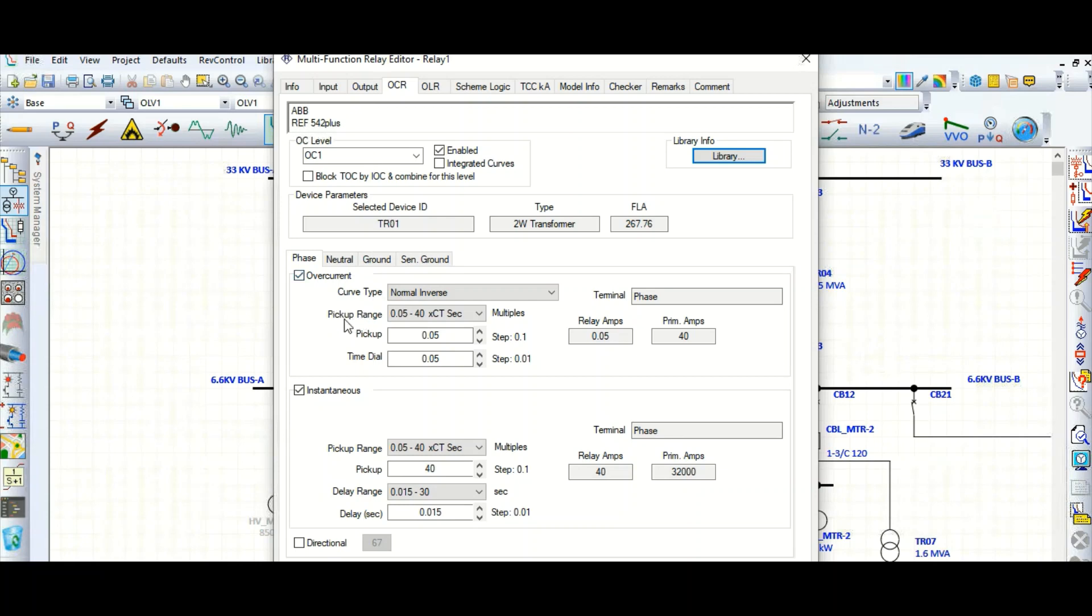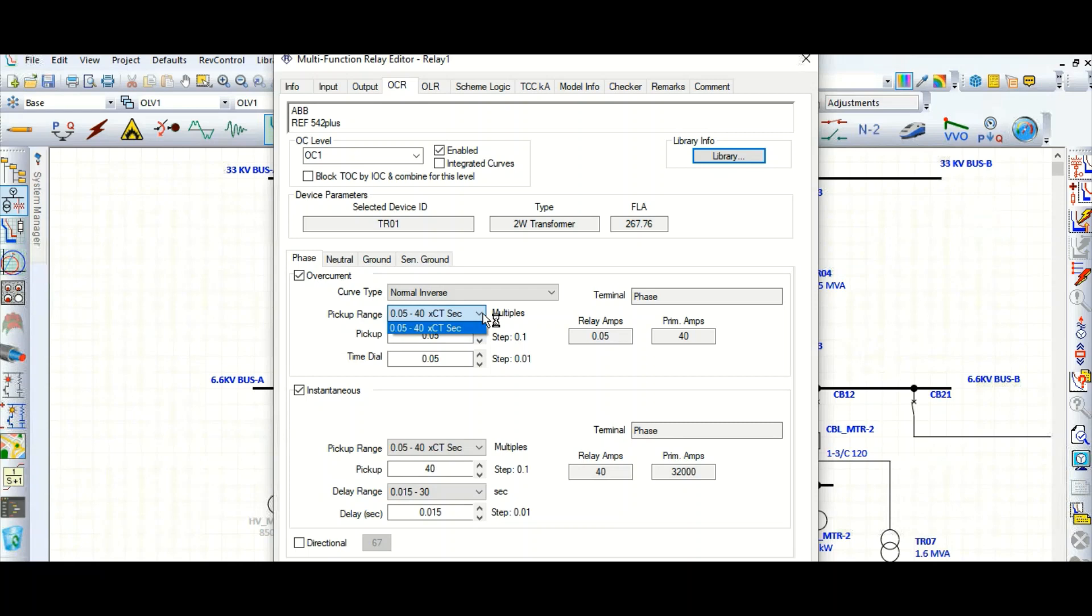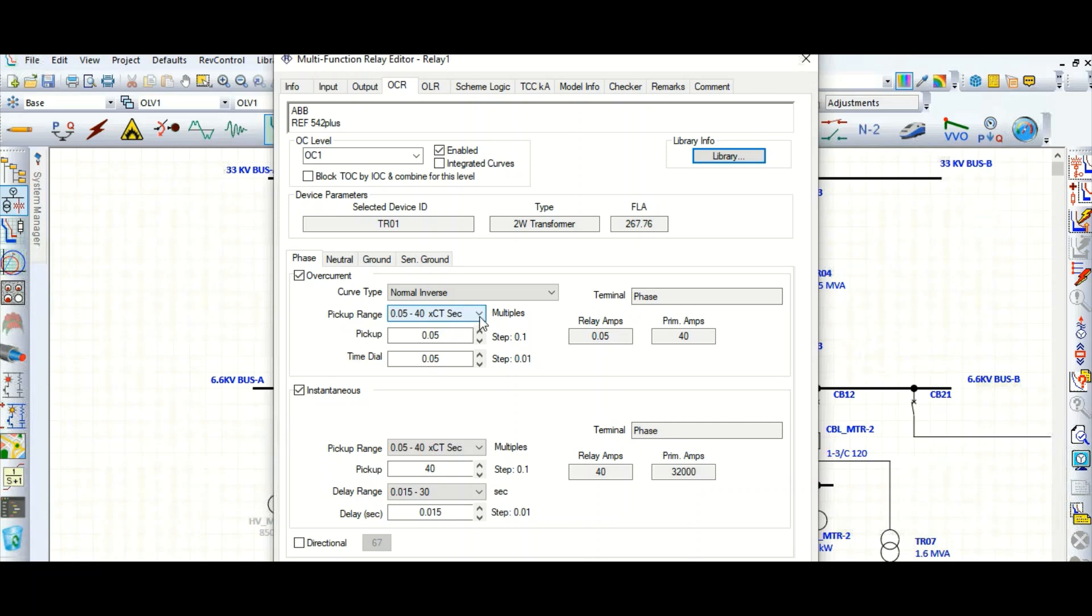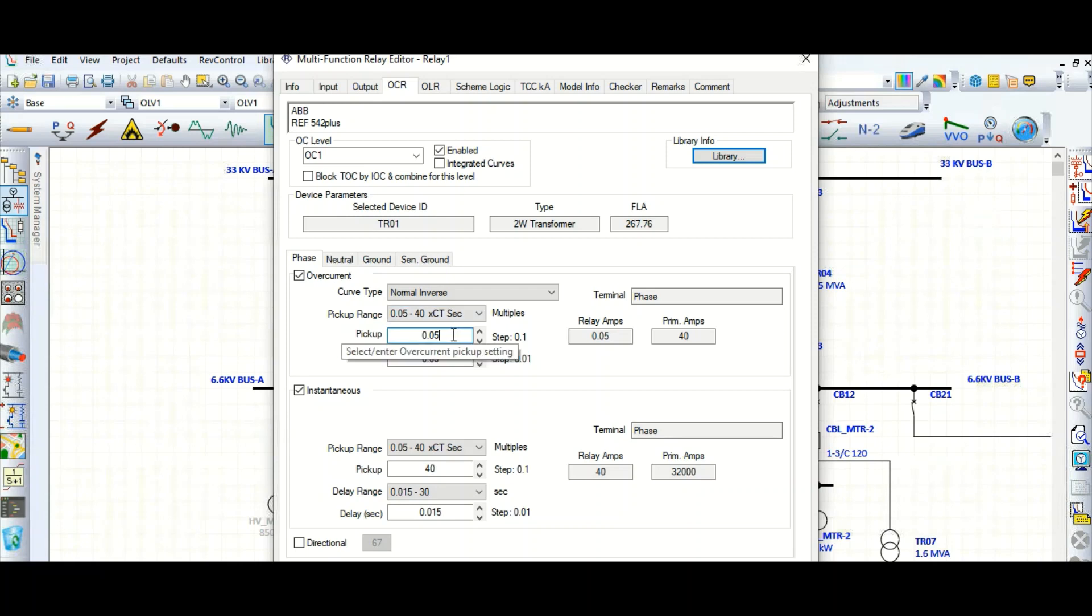This relay has the pickup setting range from 0.05 to 40. This range of CT secondary current. So you cannot go below this 0.05 and also you cannot go beyond this 40 times CT secondary current.